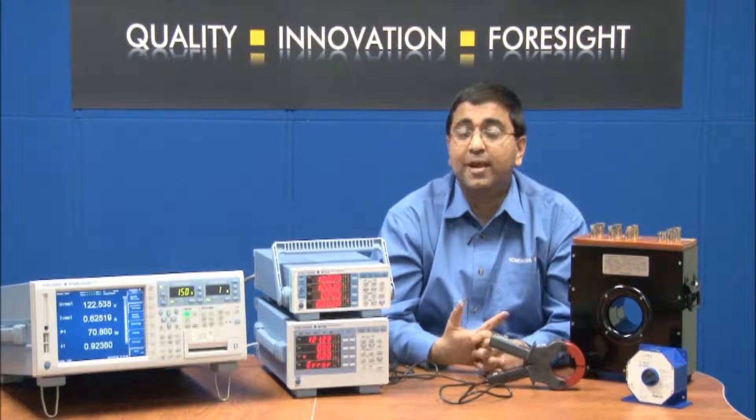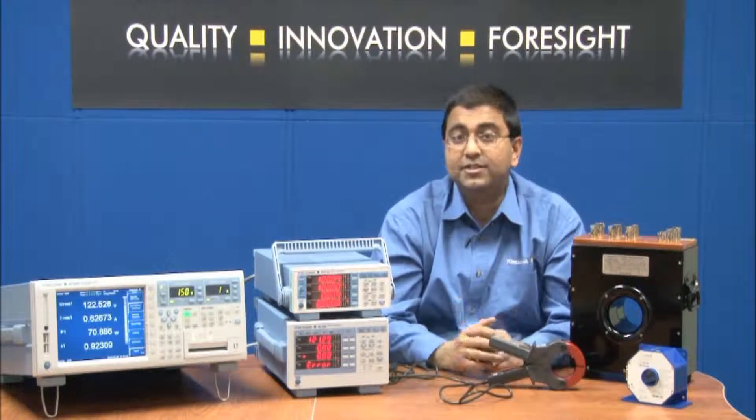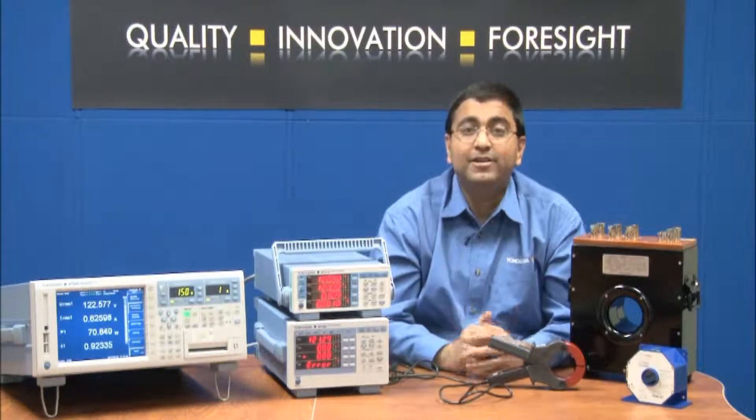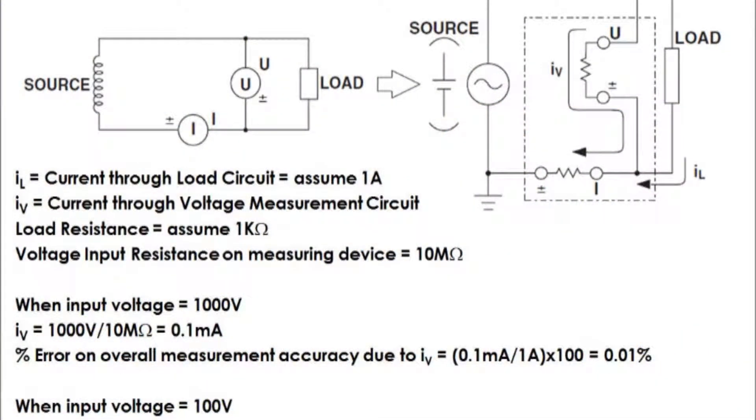Depending on the amplitude of your current signal and the input resistance of the measuring device, wiring the circuit to match the load can minimize the effects of power loss on the overall measurement accuracy. Taking Yokogawa power analyzers as an example, here is my first case.